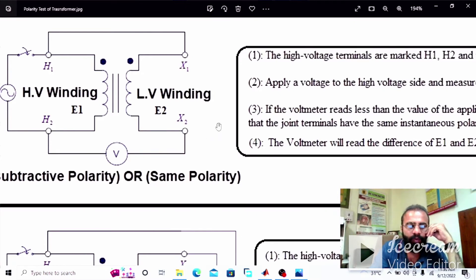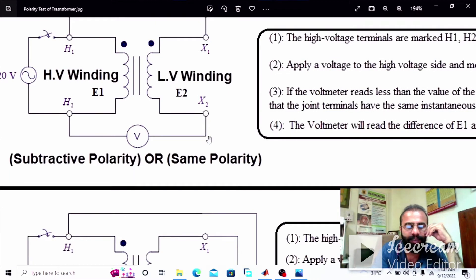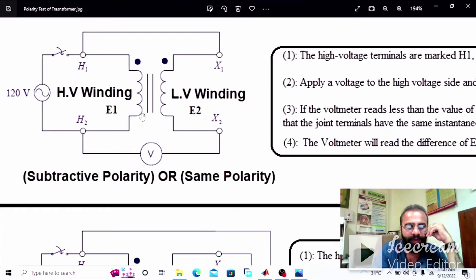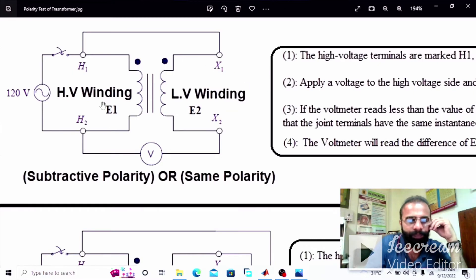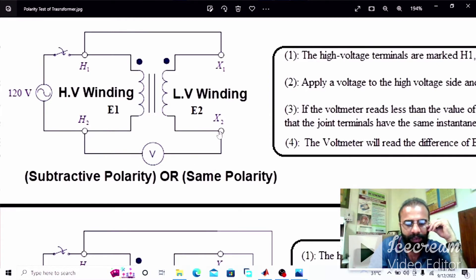Apply the voltage to the high voltage side and measure the voltmeter reading. This voltmeter is connected in between the primary and secondary winding of the transformer. When the primary winding is energized from the AC supply, flux phi M is set up in the core, causing the production of induced EMF E1 in the primary winding and E2 in the secondary winding. When connected in the same polarity, H1 is connected with X1 and H2 is connected with X2, so the voltmeter will give us the difference, less than the applied voltage.